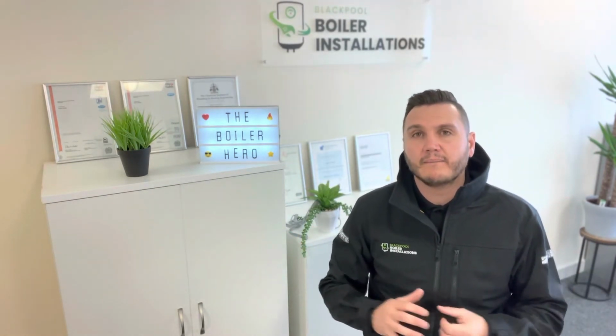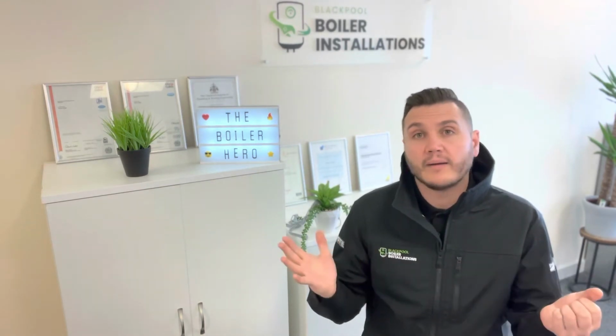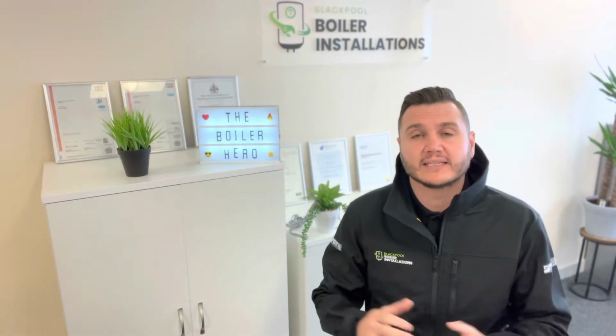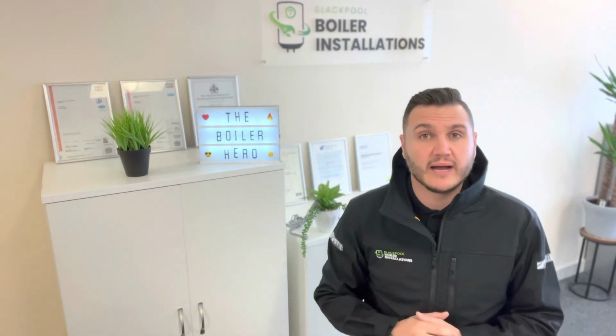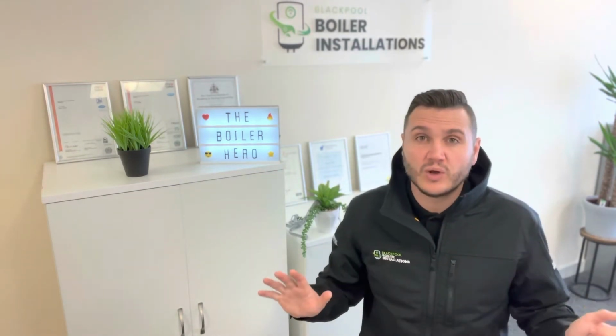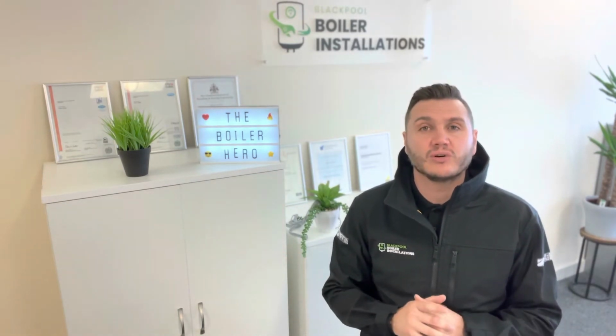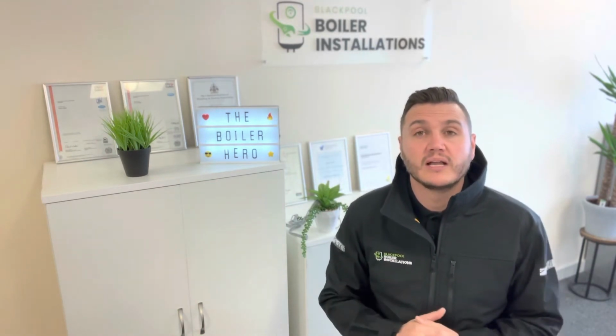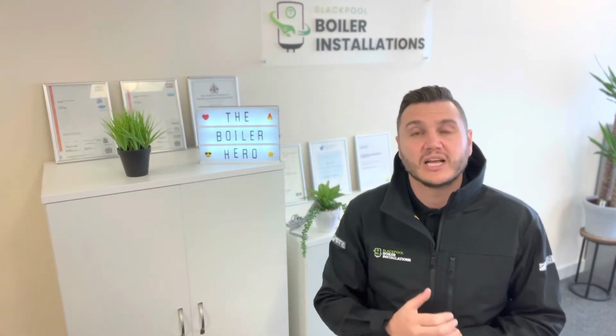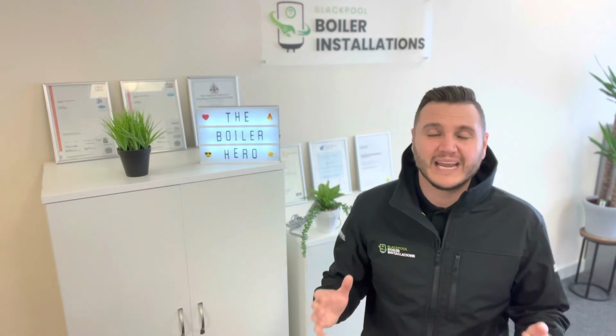Another question we have sometimes is, since you've fitted a new boiler, a couple of the radiators don't work down that far end of the house. Why might that happen? When we drain the central heating system, obviously we drain all the water out so we can work on the system. When we fill the system back up, we check everything's working as it should. However, if the odd radiator is not working, it could be because during the draining process and our work, some of the old dirty water and sludge has dragged through and one of the valves or radiators has either become blocked or it's not working as it should.